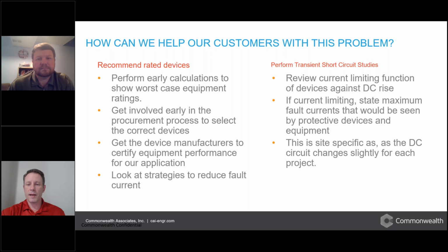But if it's already done and halfway built or the equipment's already specified, sometimes we can do the transient analysis I was talking about a minute ago. So we use current limiting fuses to try to shut down the fault current before it rises all the way. Instead of the steady state maximum fault current, we would see maybe half of that or a little bit less, sometimes significantly less. But for DC, that fault current rise time depends entirely on the circuit and the inductance, so it's going to be completely specific to each site.